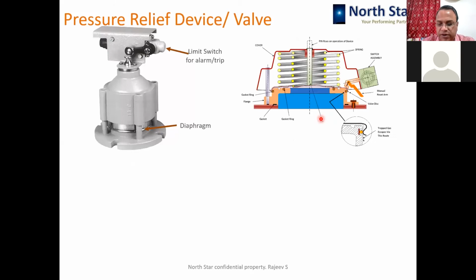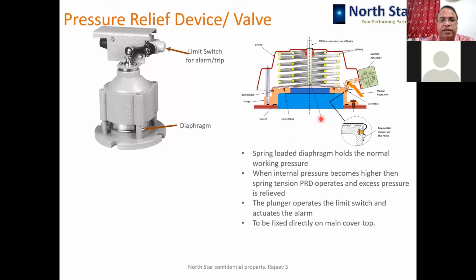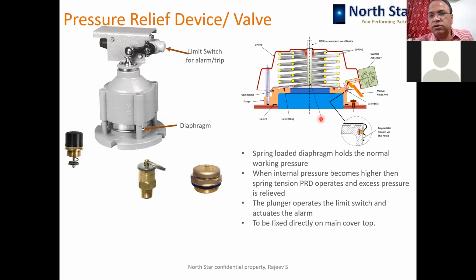Pressure relief device, these are spring-loaded diaphragms, nothing specific about it, but they play an important role as they work as a pressure relief mechanism like our pressure cooker valve. So when the pressure goes up inside, this spring gets operated and the oil comes out of the transformer. So you are keeping the transformer safe from explosion. So the transformer will not explode because of some problem in the transformer. So operation of the spring pressure relief device is to be taken very, very seriously because the excessive pressure which is getting generated can be because of some severe reason, a severe short in the transformer or some other problem.